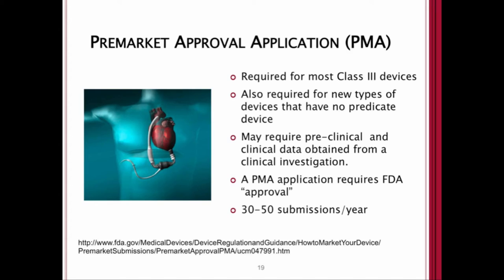Pre-market approval, or PMA, is required for most class three devices and also for new types of devices with no predicate device. It may require pre-clinical and clinical data obtained from a clinical investigation. A PMA application requires FDA approval — you submit the application, the FDA reviews, and there is an approval process. There are only roughly 30 to 50 PMA submissions per year because it is a very laborious, onerous process. There's a web link at the bottom for more information.